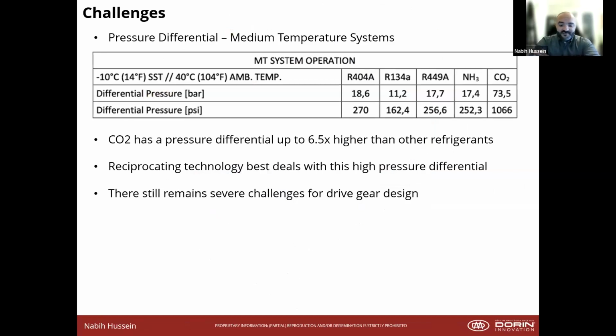It does come with challenges, as we mentioned. CO2 has a much larger pressure differential than other refrigerants. Just based off of these numbers, you see 1,066 psi differential for CO2. It's 6.5 times higher. But this just means that your compressor needs to be able to handle that. We believe reciprocating technology works best with this, but there are other technologies that also work for high pressure differentials.